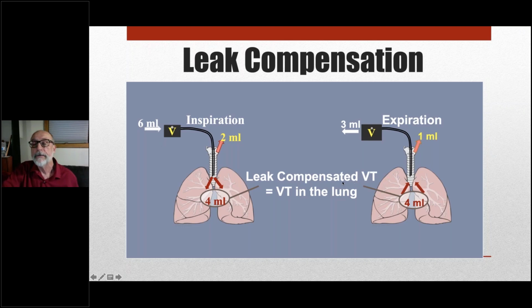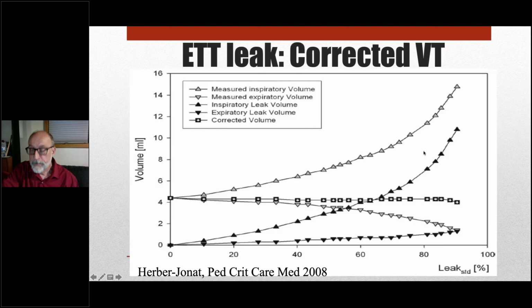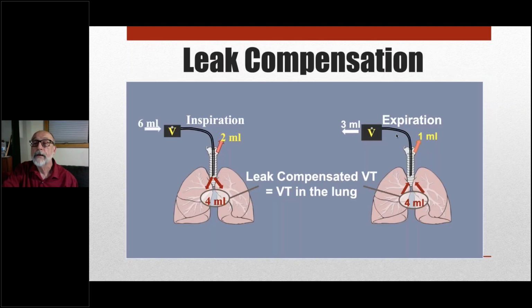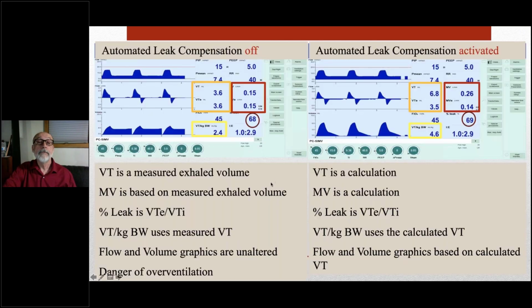But then there's also some leak during the expiratory phase. It's less because the pressure that drives the leak is less during expiration. This is, of course, driven by the PEEP, the end expiratory pressure. But let's say there's a 25% leak, and therefore the exhaled tidal volume that's measured is only 3 ml. Well, it's a 25% difference. So if you didn't have automated leak compensation, the ventilator would be chasing this number and increasing the pressure and potentially overventilating the patient. But with leak compensation, you can actually know that the lung tidal volume was 4 ml, and you can use that value.